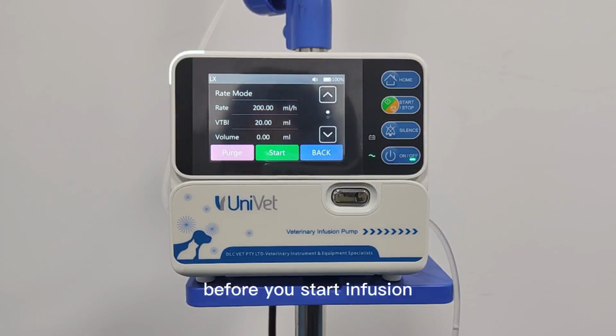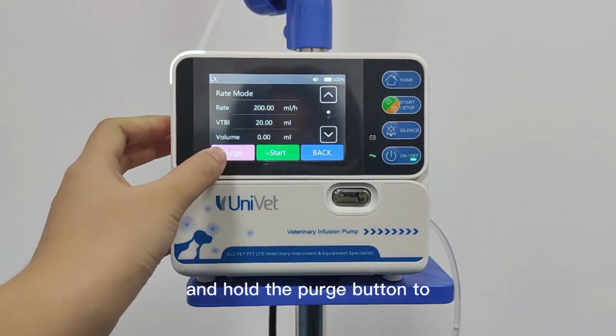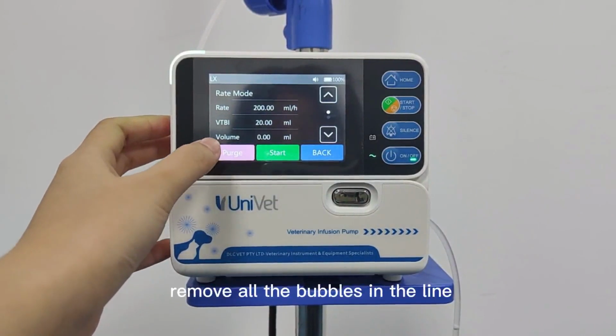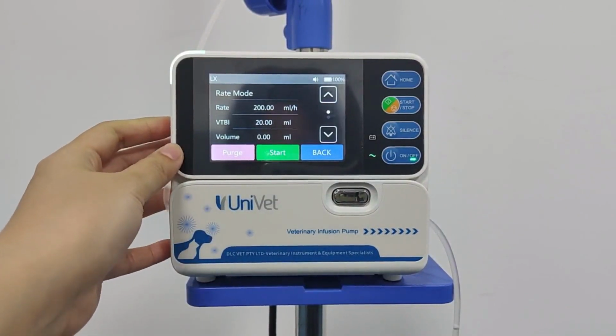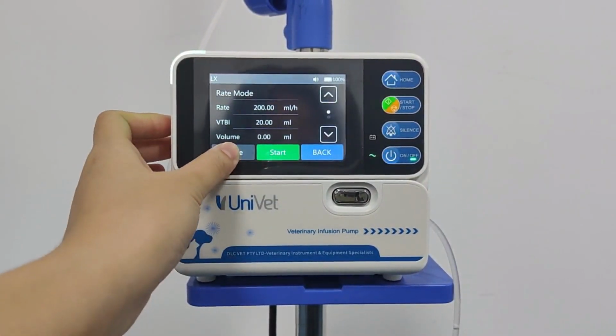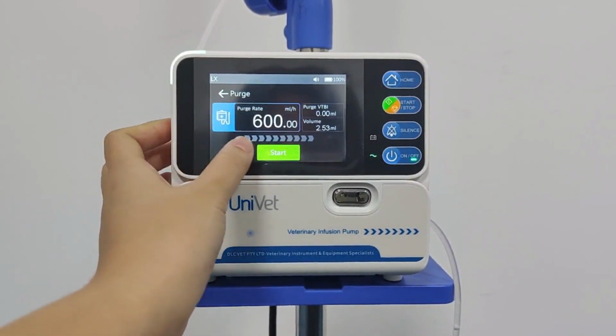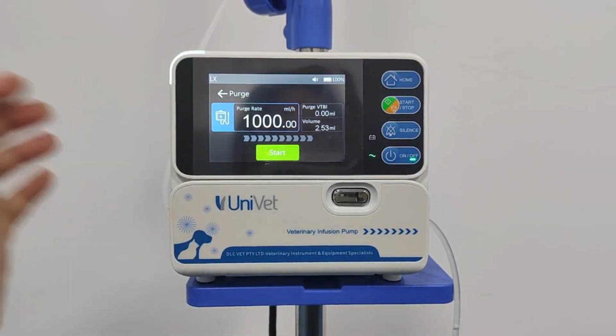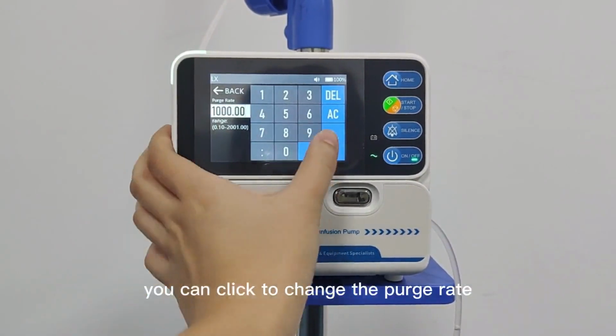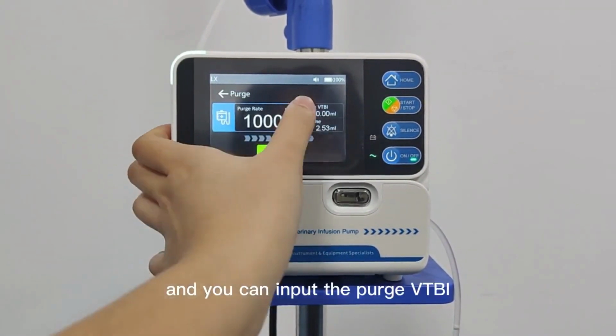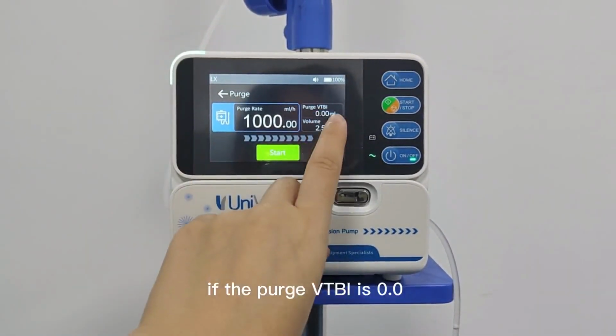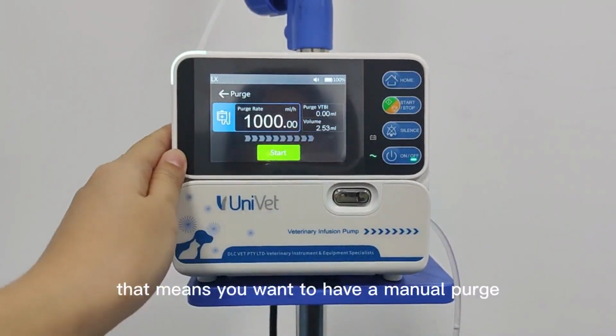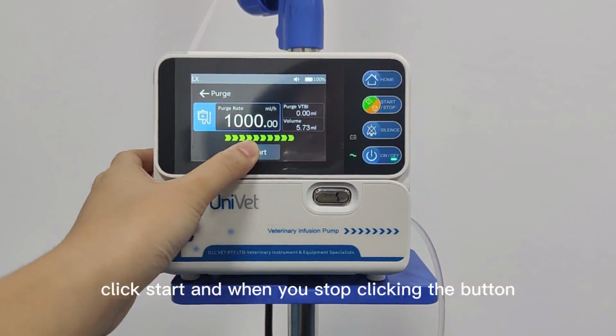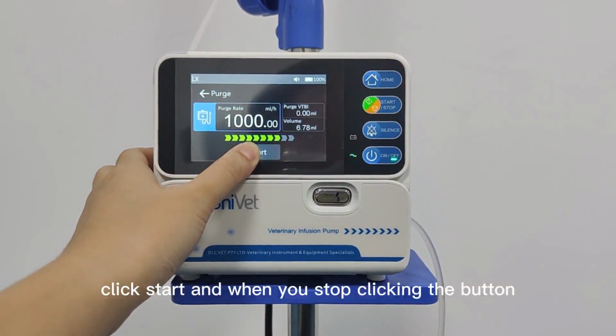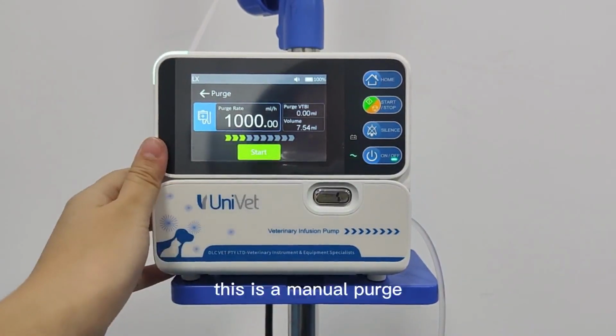Before you start infusion, don't forget to click and hold the purge button to remove all the bubbles in the line. You can click to change the purge rate. And you can input the purge VTBI. If the purge VTBI is 0.0, that means you want to have a manual purge. Click start. And when you stop clicking the button, the purging stops. This is a manual purge.